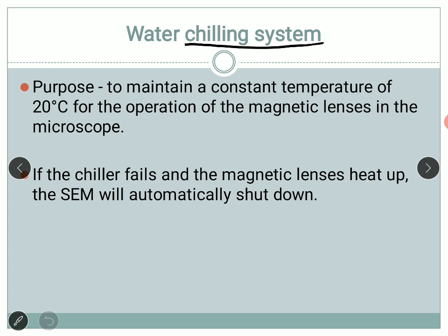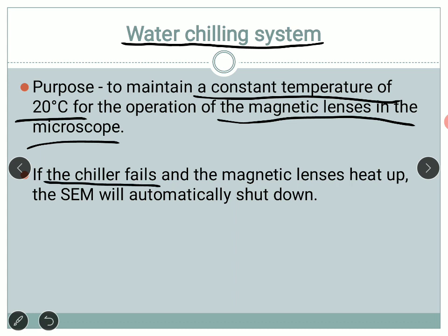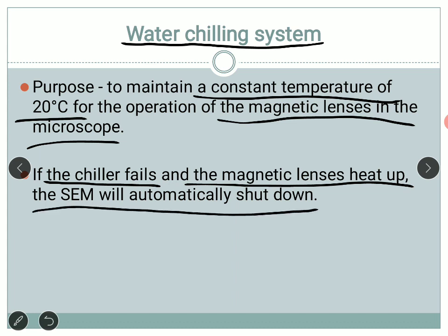The next part of the instrument is the water chilling system. As the name suggests, it keeps the system cool. Using many magnetic lenses with a power source and electromagnetic fields causes heat. It is very important that the temperature of the system be constant and maintained at around 20 degrees centigrade. Rooms housing SEM instruments always have AC fitted. If the chiller fails and temperature rises, the magnetic lens heats up and the SEM will automatically shut down.